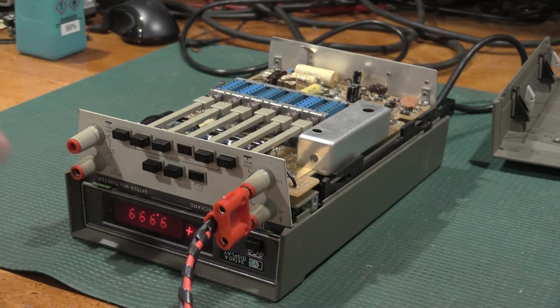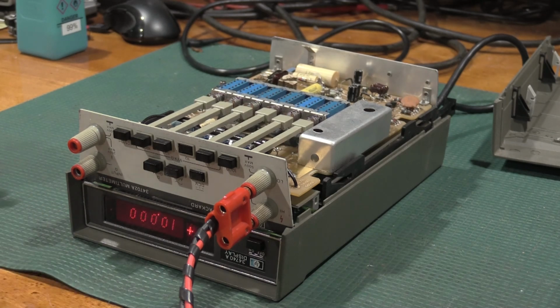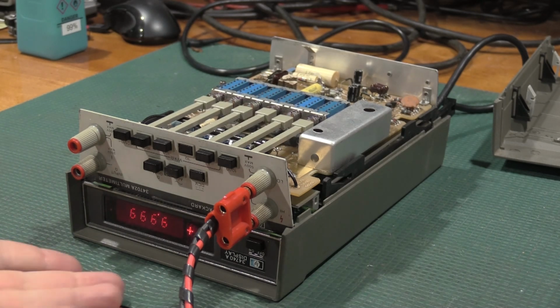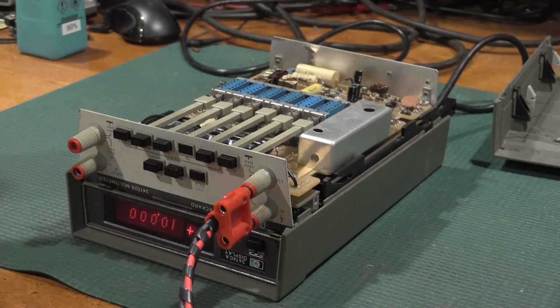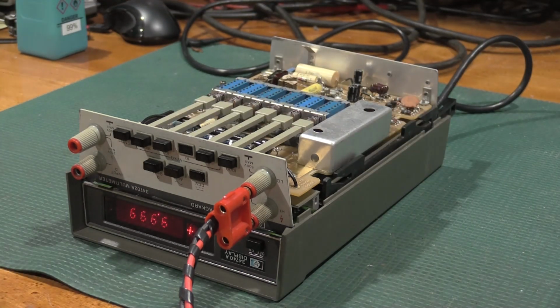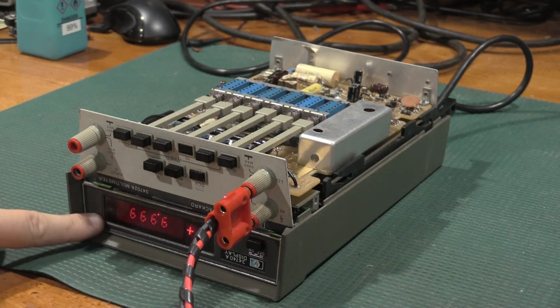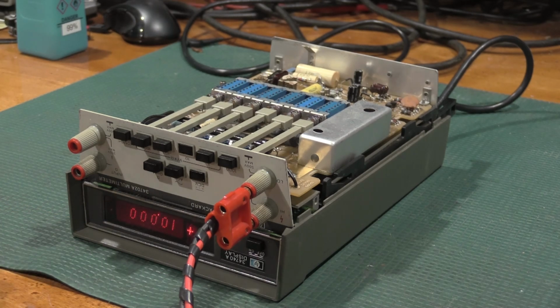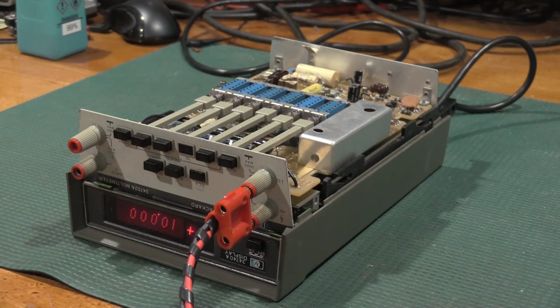Well, when we have a meter cable that works, it works a little bit better. We'll let this warm up a little bit more before we do the alignment, because I did have it off for a little bit, so it does need some warm-up time. This is looking pretty good for the 10 volt range. Well, looks like we can leave the 10 volt range alone. Let's check the 100 volt range.